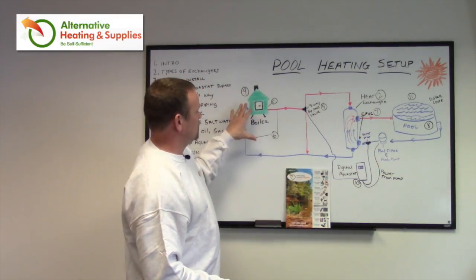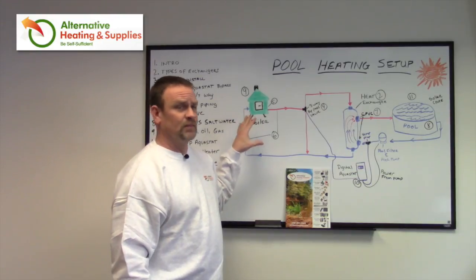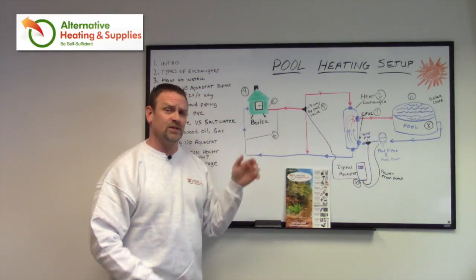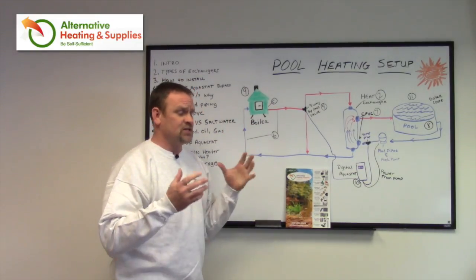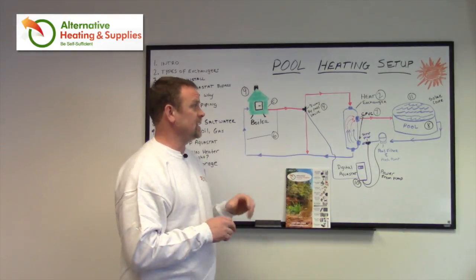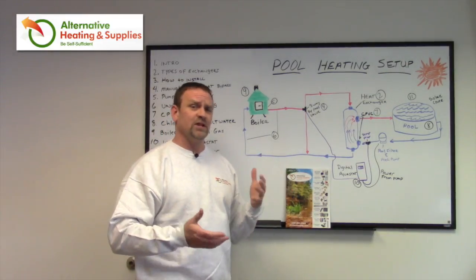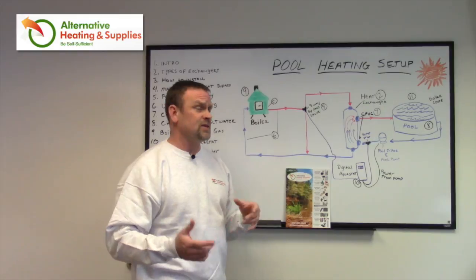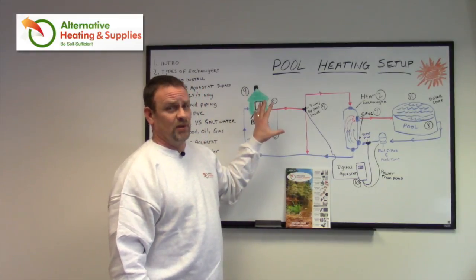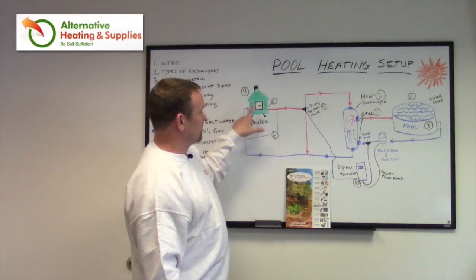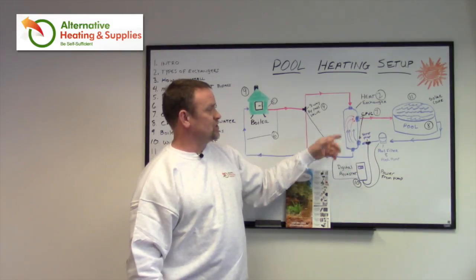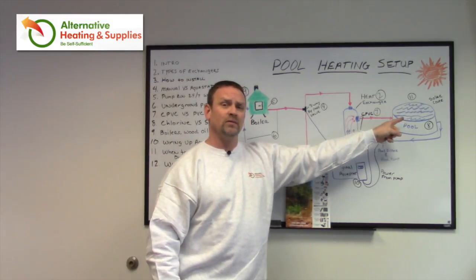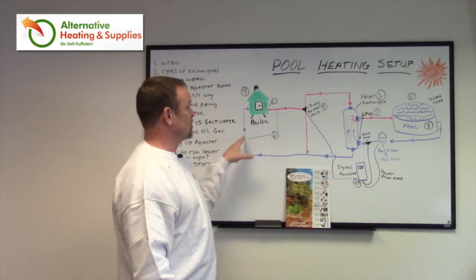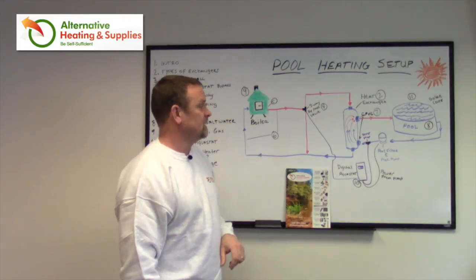It's now hooked to a conventional heating boiler. This could be your indoor boiler, your outside wood boiler, or a boiler of any kind. The water temperature of a boiler runs anywhere from 160 to 180 degrees. That's all we need to accomplish. So the water from the boiler goes through the heat exchanger, which exchanges the heat to the pool water, putting it back into the pool, and then returns to the boiler to be reheated.